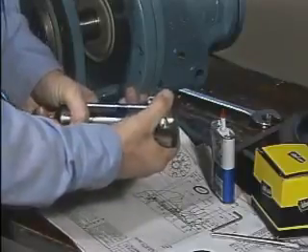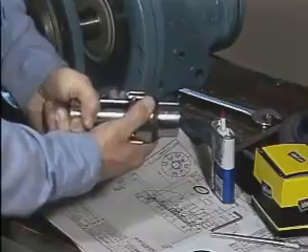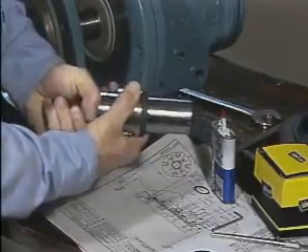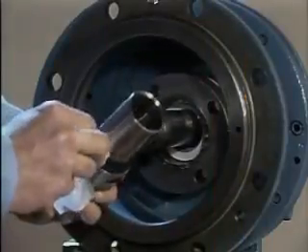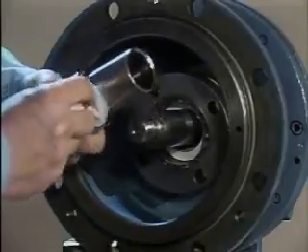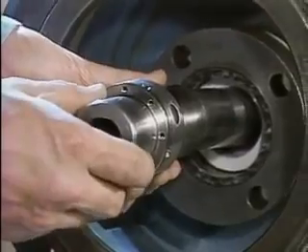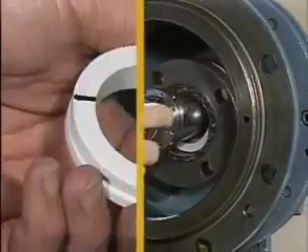One of the most frequent installation problems has to do with the positioning of the rotating element. If the rotating element isn't positioned properly, the seal will almost certainly fail prematurely. The mishandling of seal components before and during installation can also lead to seal failure. The seal faces are among the easiest components to damage by mishandling because they're usually quite brittle.